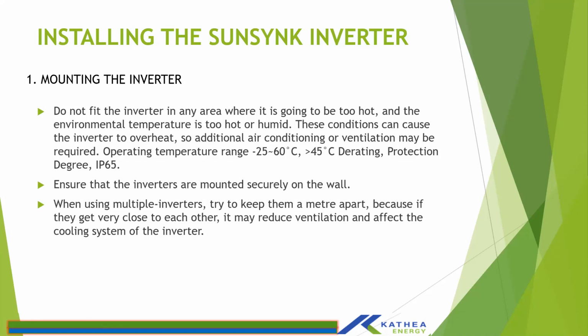So if you are to install the inverter in a confined area, let's say in a closed room, it's advisable to also install an air circulation mechanism or an air con, such that it can cool the environment. Because the moment the temperature goes above 45 degrees, the inverter will start derating. When installing it, make sure it's installed on a firm platform or on the wall.